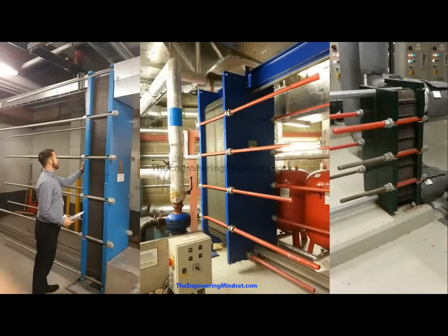Now you'll probably notice that the tightening bolts extend far past the heat exchanger. That's for a few reasons. One is to be able to fit all the plates on during installation or maintenance, but it also gives you the ability to extend the plate heat exchanger in future. This one, for example, is from a district heating network, and at the moment the building is only half complete and they're expecting to double the building size, so they've allowed extra bolt length to be added, meaning plates can be added and the heat exchanger can grow with demand.